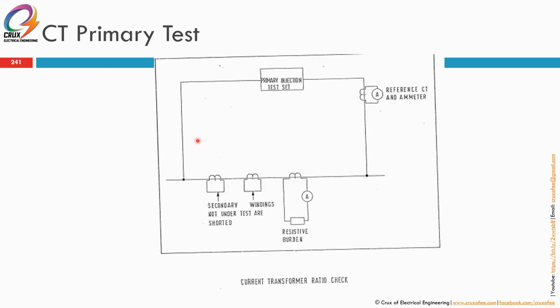Okay. So CT primary test, this is to test the ratio test. So you'll have a primary injection test set. For example, if this is a 40/5 amp CT, you will inject 40 amps on the primary. On the secondary, you should be reading 5 amps, and you also have a reference CT and meter just to verify that. Make sure that this is also reading 5 amps on the secondary. Okay, so this is the ratio test, to confirm the ratio of the CT.